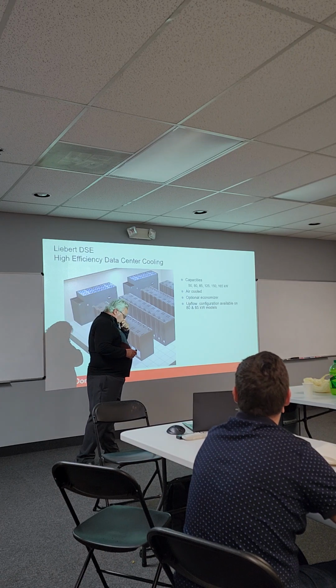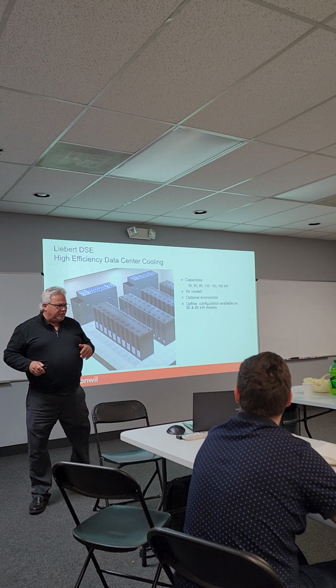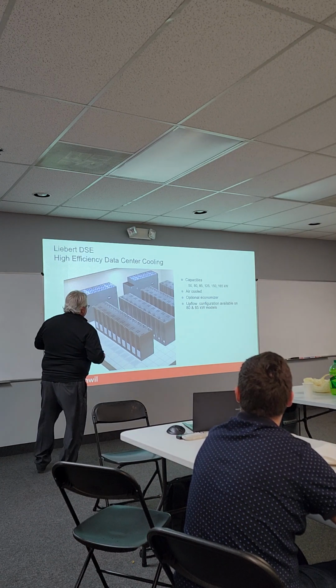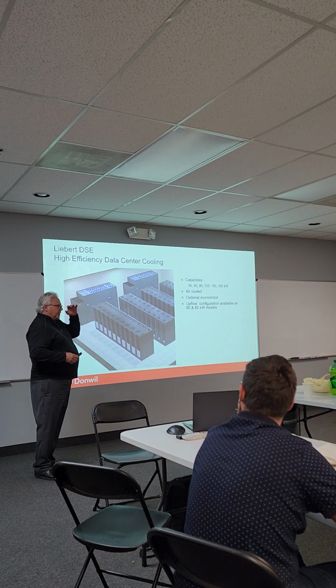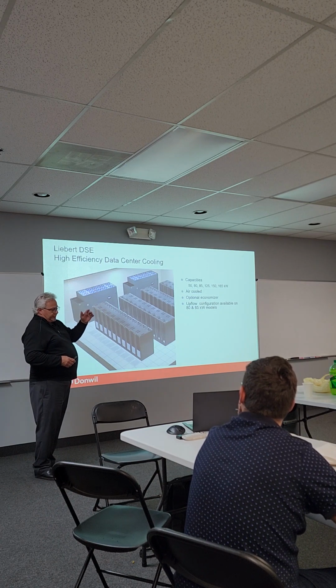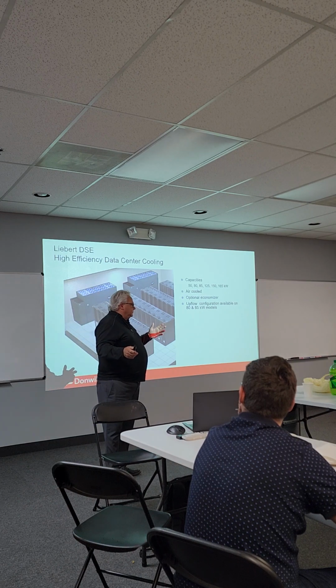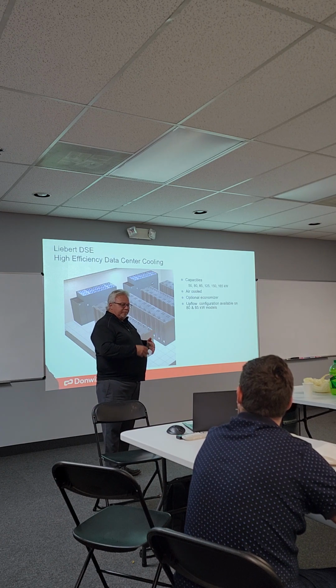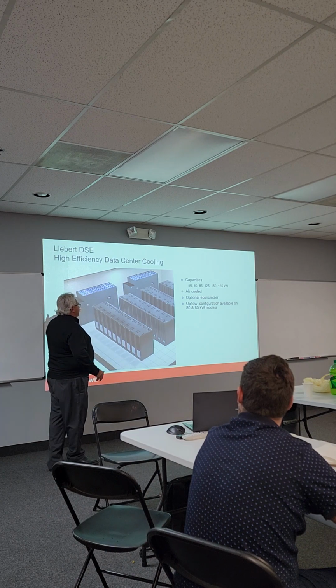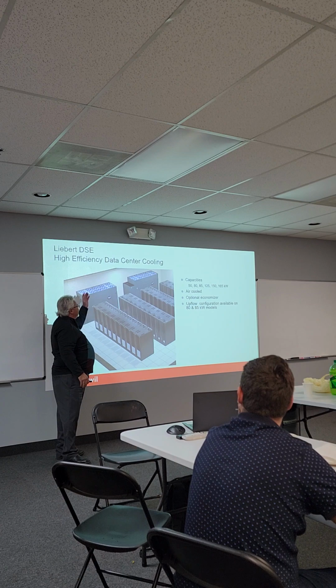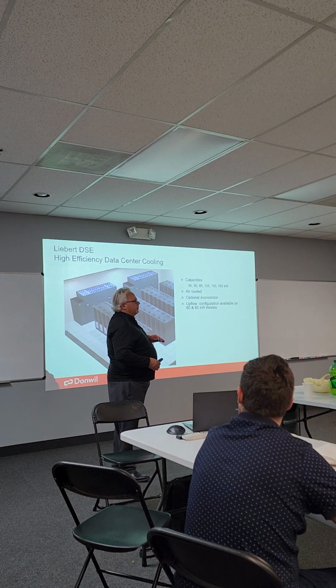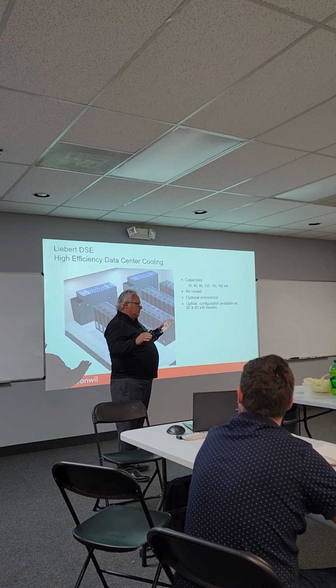Well, here's the thing. A lot of people say, I can do free cooling for a computer room. I can use atomization, I can do some kind of water, I can open an economizer, I can put an air handler with an economizer in it and bring in fresh air. What happens when you do that? You bring in humidity if it's summertime, or you're bringing in real dry air, right? Consequently, you're going to make that Liebert unit work really hard, because it's trying to satisfy whatever you're bringing in. So that's why on an unmanned computer room, we tell everybody, no outside air at all. Nothing. In some cases you have to have it, because if it's a manned computer room, then you're going to have to have outside air.